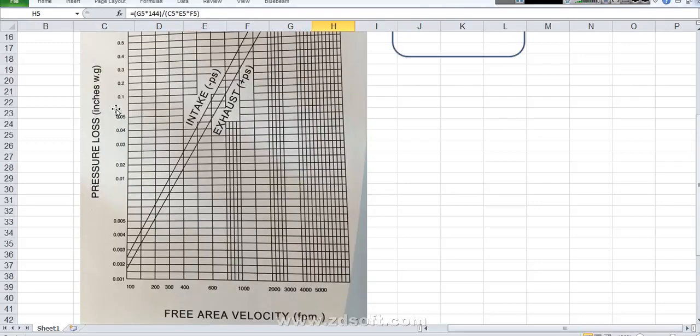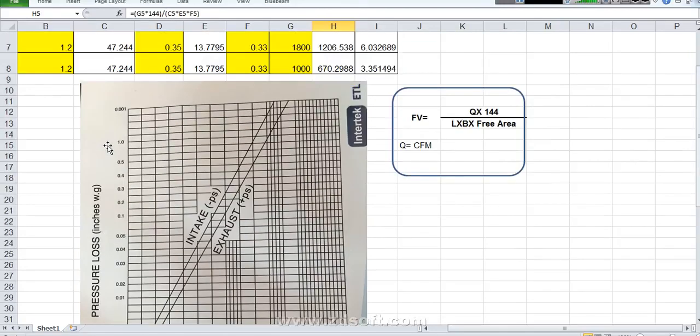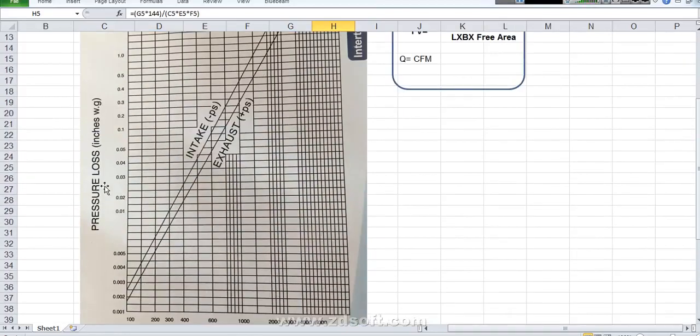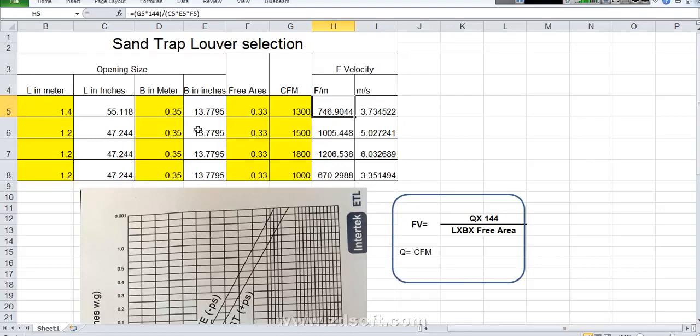So the pressure loss is 0.1 inches of water column. This is inches of water column of course. Inches of water column here see. This is the pressure loss for the Sand Trap Louver. When we are doing ESP calculation we can use this pressure loss. What is the result is here. Here this one we can directly put in ESP calculation also.